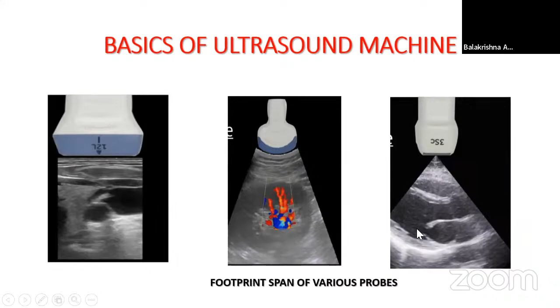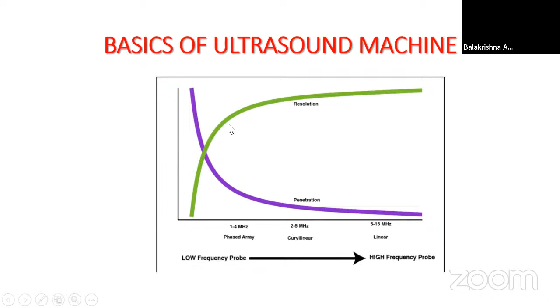This graph is self-explanatory. It shows that as the frequency increases, that is from a curvilinear to a linear, the resolution increases, but the penetration decreases. So on the basis of this graph, we see that when the frequency increases, the penetration reduces. So that is where we get to use the linear probe. And as and when the frequency reduces, the depth increases. So we get to use the curvilinear probe, which is somewhere between 2 to 5 megahertz, to visualize the deeper structures.